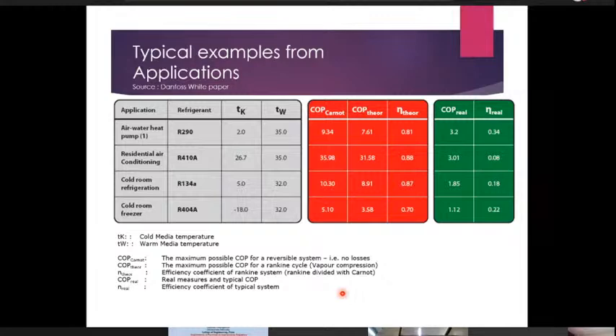So this chart, then again, we can look at cold room refrigeration. So again, the cold room refrigeration, what is it? What are the two temperatures? The temperature that we desire and the temperature to which we must reject heat. And we see 0.18 versus 0.87, 0.22 versus 0.70 for cold room freezer. So we can easily see a huge opportunity no matter which system we are looking at.